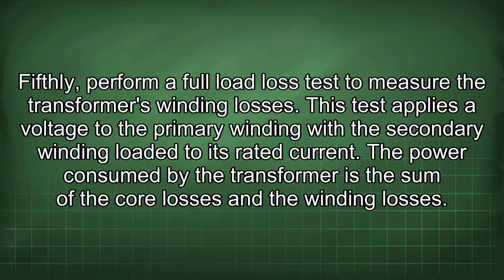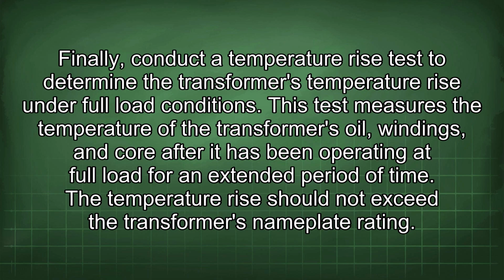Fifthly, perform a full load loss test to measure the transformer's winding losses. This test applies a voltage to the primary winding with the secondary winding loaded to its rated current. The power consumed by the transformer is the sum of the core losses and the winding losses. Finally, conduct a temperature rise test to determine the transformer's temperature rise under full load conditions. This test measures the temperature of the transformer's oil, windings, and core after it has been operating at full load for an extended period of time. The temperature rise should not exceed the transformer's nameplate rating.